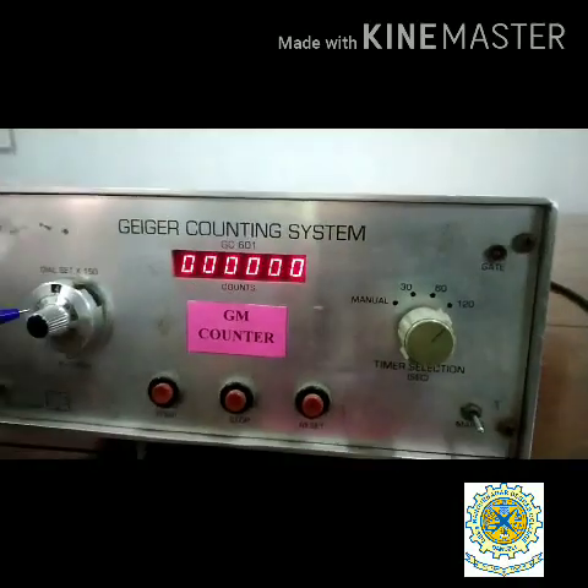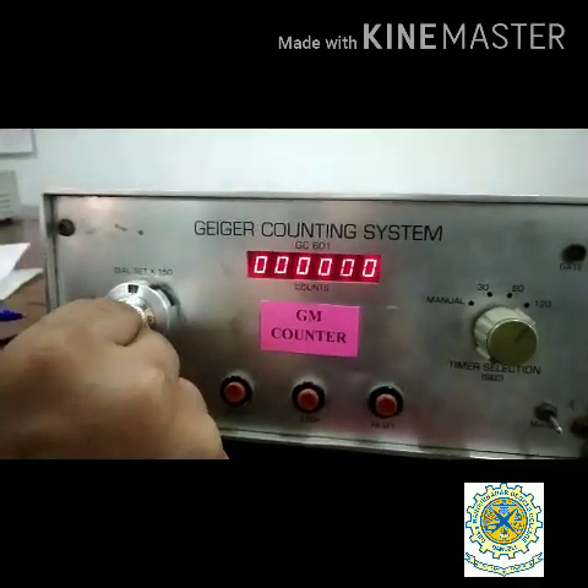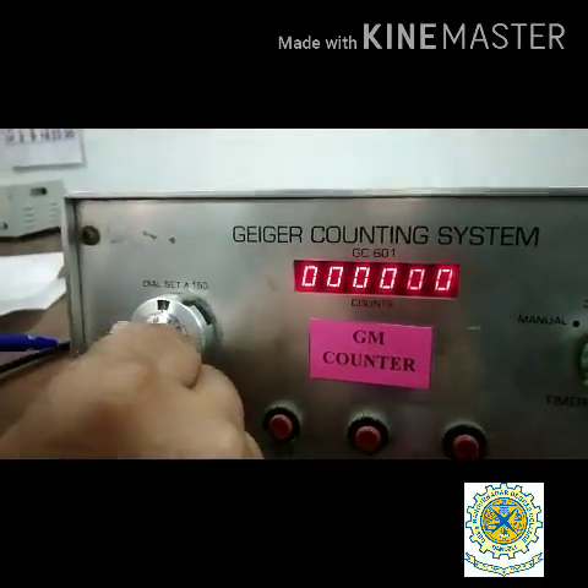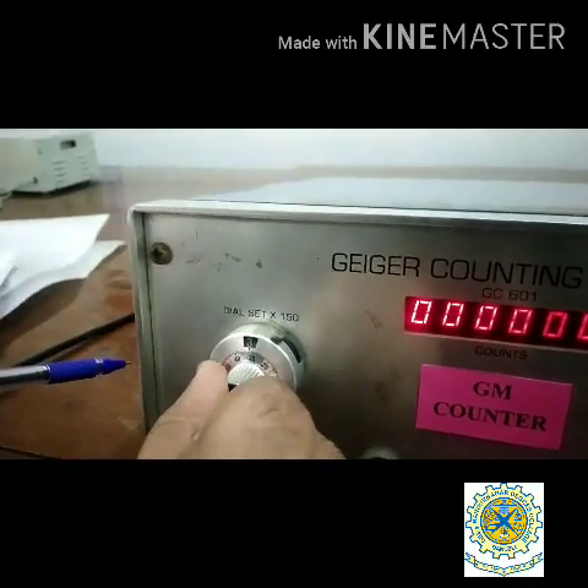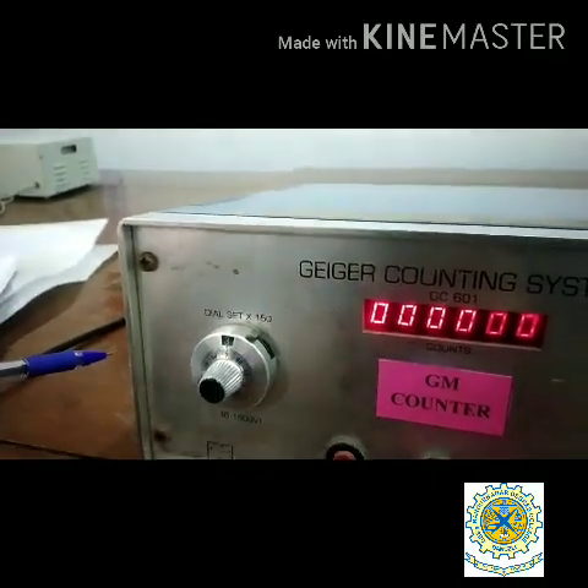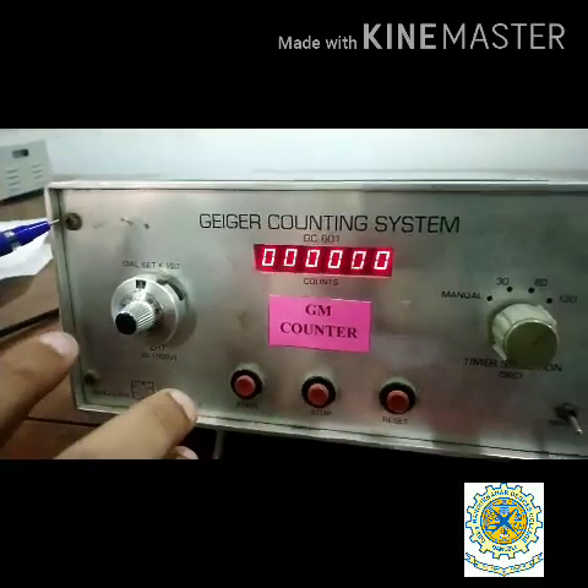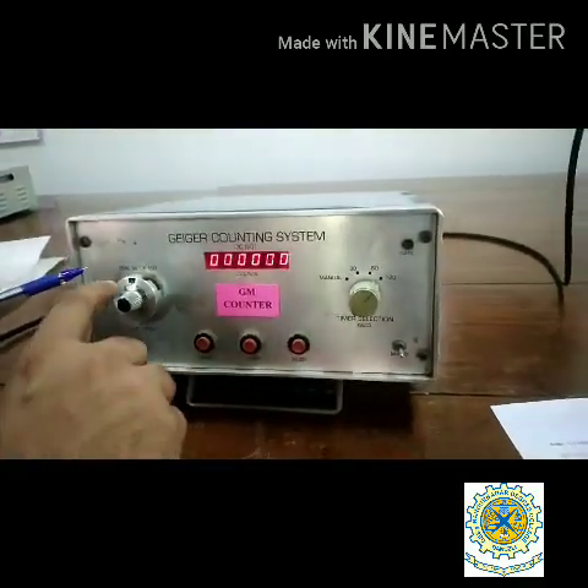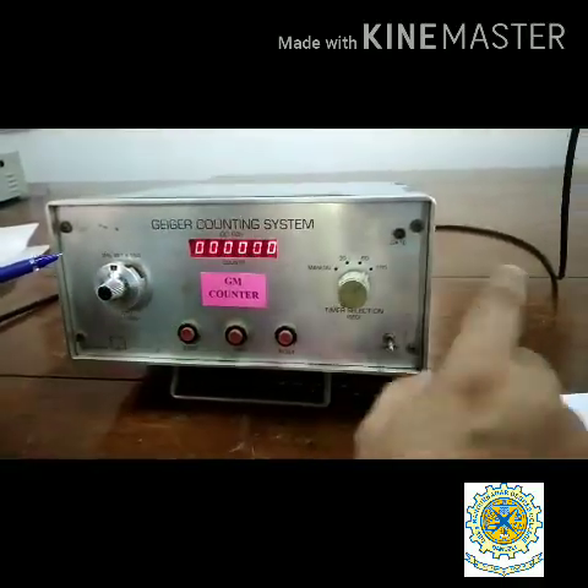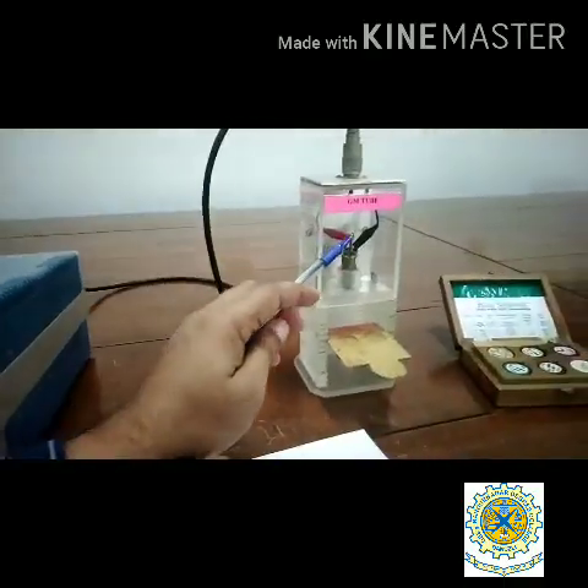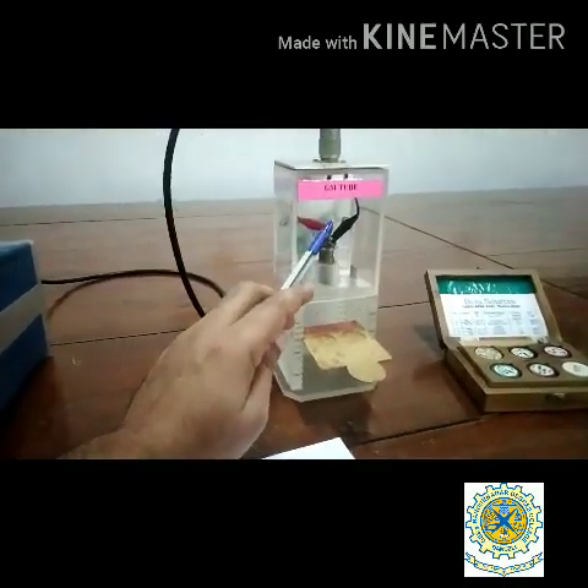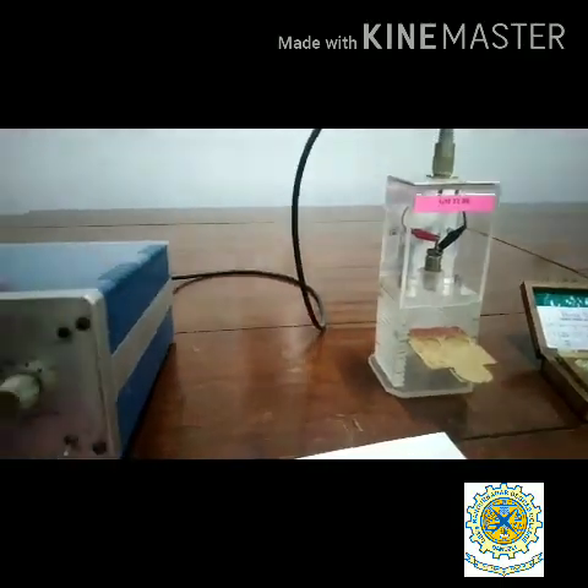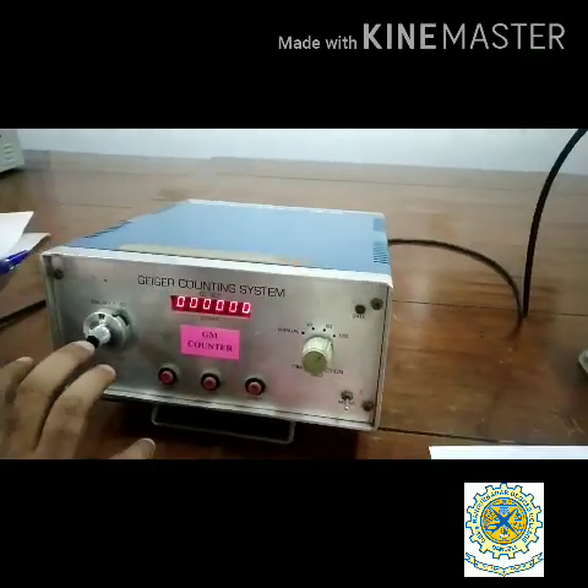And if I reduce it to 3, then we have set a voltage of 3 into 150, which is 450 volts, built here in the GM tube between cathode and anode. So this is a dial set which works like this.